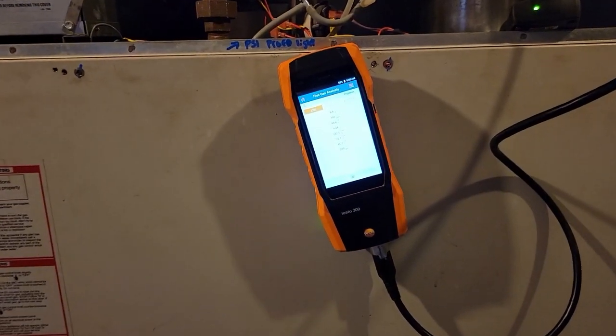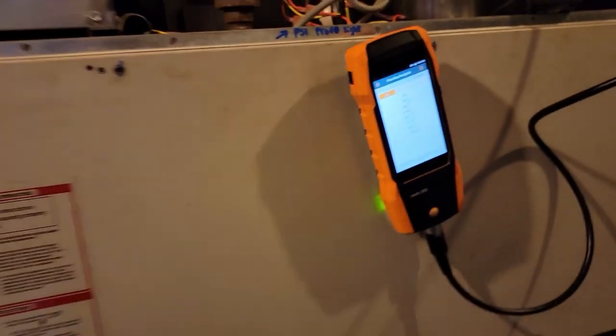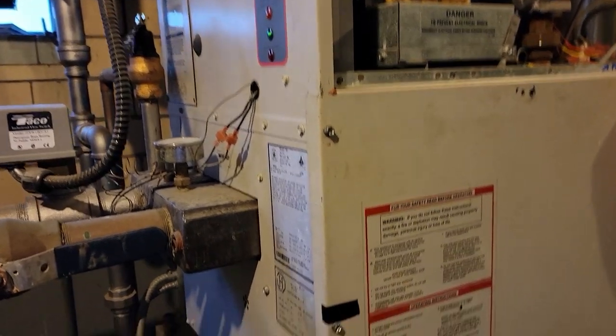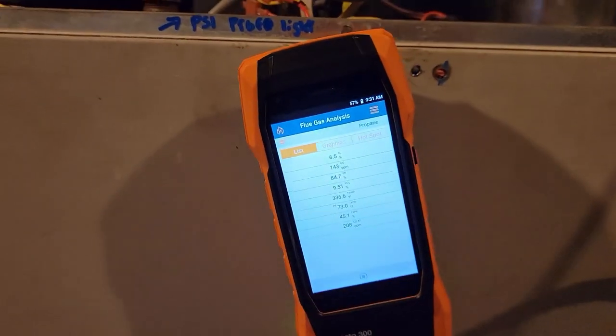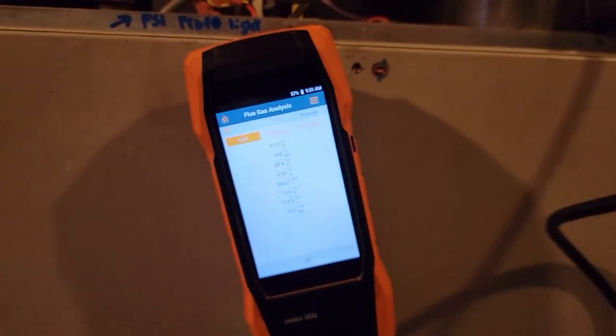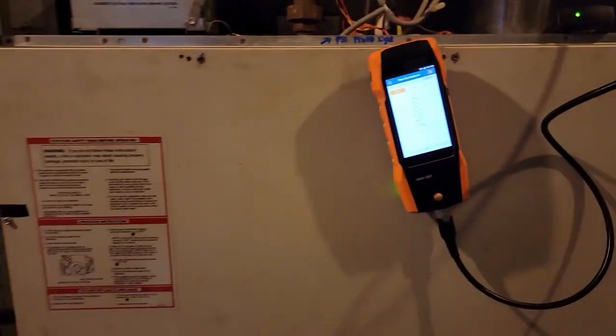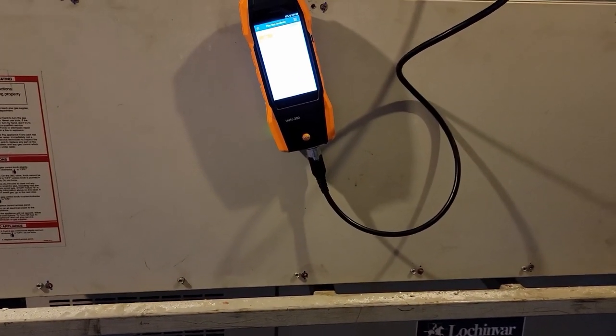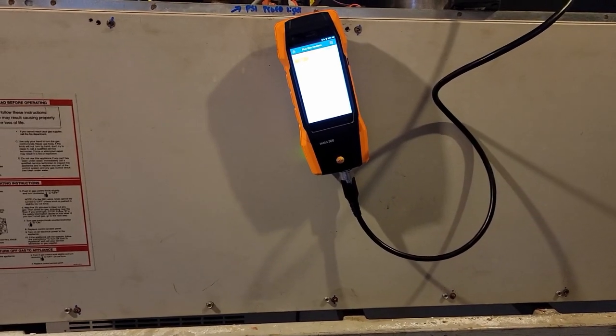We're back a different day. They called in, said it tripped out, but then he reset it and it's been running fine since. However, looking at the flame it doesn't look all that great. We were running right at 140 CO, so it's technically where the factory said it was going to be at. We're going to clean these burners out, we're going to wash them out, and then adjust whatever we got to adjust to try to get it where we want it at.